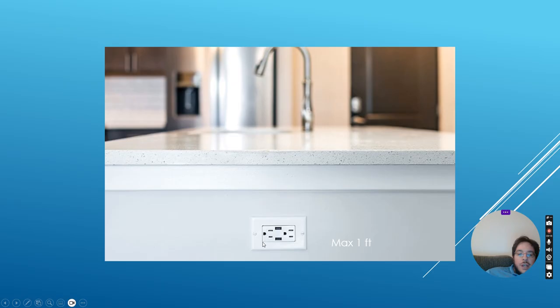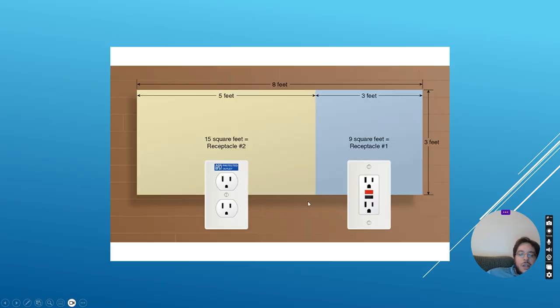Now, if you've got an island, then you need a receptacle for your island, and there's certain rules depending on the size of the island. Now, receptacles can be installed sideways, but if they are, then the neutral, which is the bigger hole, has to be facing up, and that's designed so that if something falls down into the receptacle when something's plugged in, it doesn't start a fire. And you must be a maximum of 1 foot from the top of the counter. Now, if you've got a sink in Canada, then this has to be GFCI, like I said, and in the United States, it always has to be GFCI or AFCI.